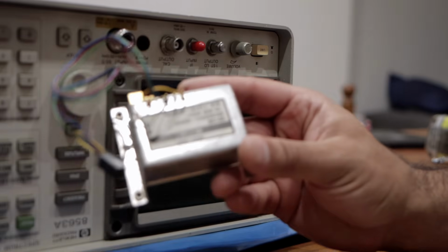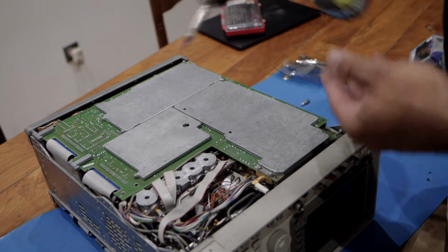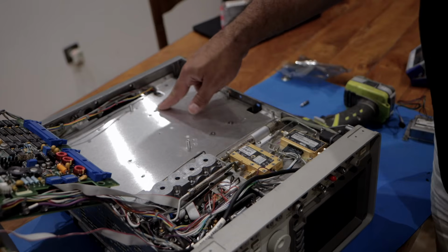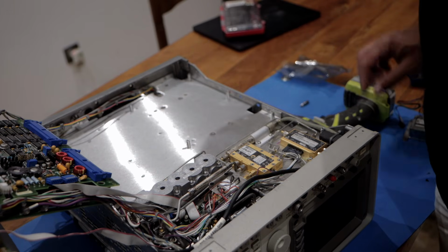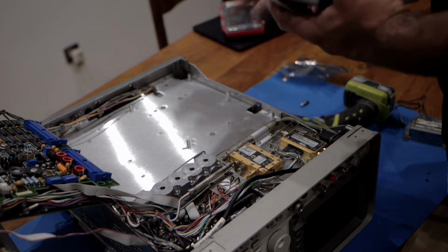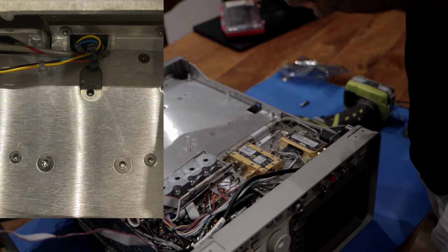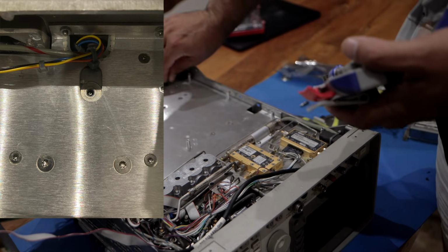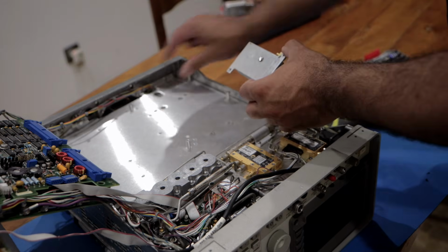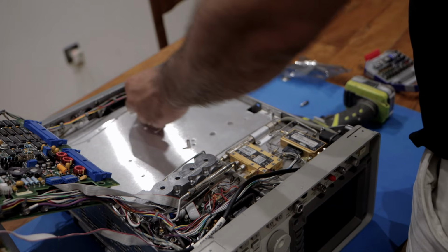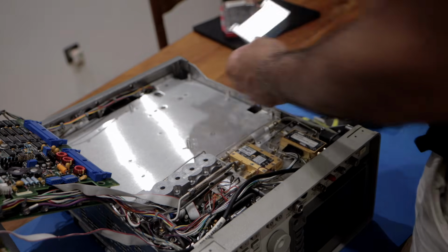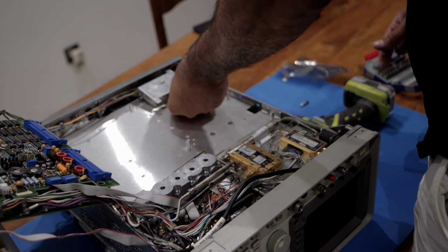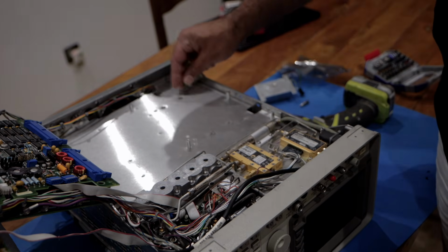Now, let's swap out the old one and install the new oscillator. Back to the RF side. First, I need to unscrew the old 821 oscillator. While identifying the three screws I had to remove, I noticed the trimming cover was missing. Maybe someone tried to kickstart the oscillation by tweaking the trimmer? At least it was a red flag from the start that something was wrong with this oscillator. But I totally missed it. By double checking if the new oscillator will fit, I can confirm the trimming cover is there as well. Let's remove those screws now.